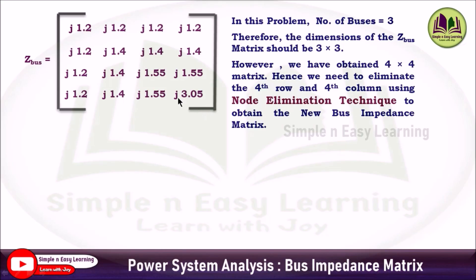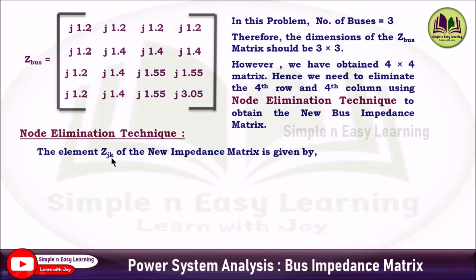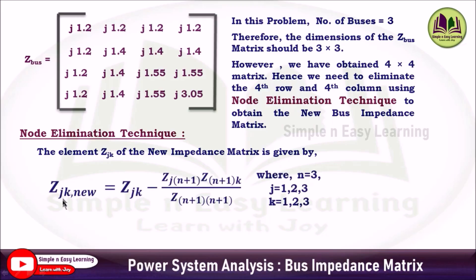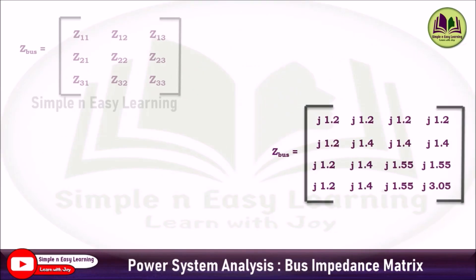Observing this matrix, it is 4×4 but the problem has only three buses, so the final answer must be 3×3. We need to reduce this 4×4 matrix to 3×3 by applying the node elimination technique — eliminating the fourth row and fourth column. The formula is: Z_jk(new) = Z_jk − (Z_{j,n+1} × Z_{n+1,k}) / Z_{n+1,n+1}, where n = 3, and j and k each vary from 1 to 3.